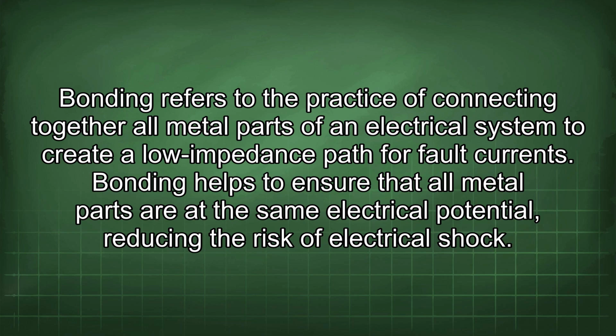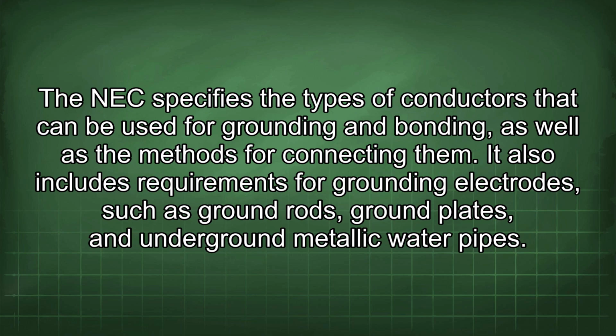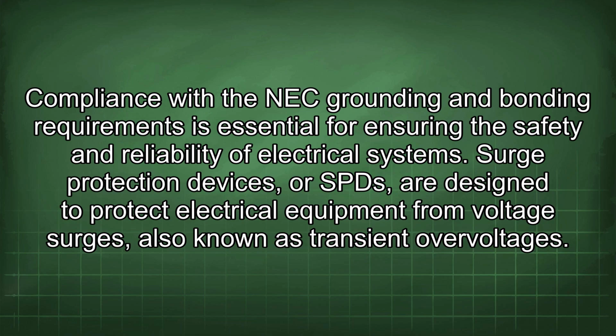Bonding refers to the practice of connecting together all metal parts of an electrical system to create a low impedance path for fault currents. Bonding helps to ensure that all metal parts are at the same electrical potential, reducing the risk of electrical shock. The NEC specifies the types of conductors that can be used for grounding and bonding, as well as the methods for connecting them. It also includes requirements for grounding electrodes such as ground rods, ground plates, and underground metallic water pipes. Compliance with the NEC grounding and bonding requirements is essential for ensuring the safety and reliability of electrical systems.